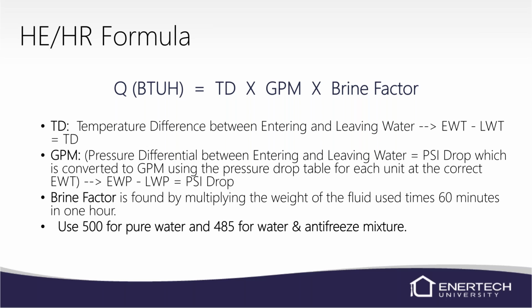But that's kind of stupid. I don't think you're going to weigh the fluid and do all that. Basically, the easiest thing to know is use 500 for your brine factor for pure water, and use 485 if you've got an antifreeze and water mixture. So if you've got a closed loop with antifreeze in it, use 485.